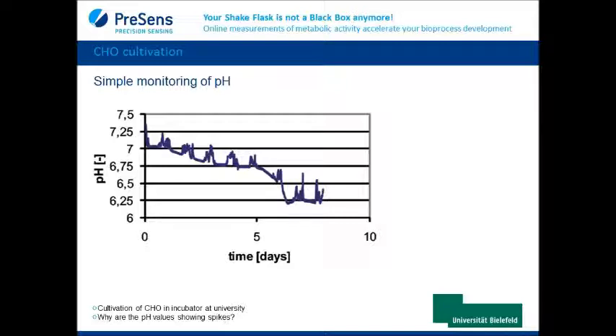This was an incubator that was used by various guys who did their PhD at that time in that lab. And it's day and night. So the parts with the spikes are the days where all the other guys opened the incubator. And you can see that this has already a severe impact on your pH value because you lose all the CO2 atmosphere. So what our system would enable is that you could do an online measurement of pH, O2 and biomass where you do not have to open your incubator and you do not have to draw a sample, and you could foreclose those spiky curves and you can foreclose those impacts on your culture.